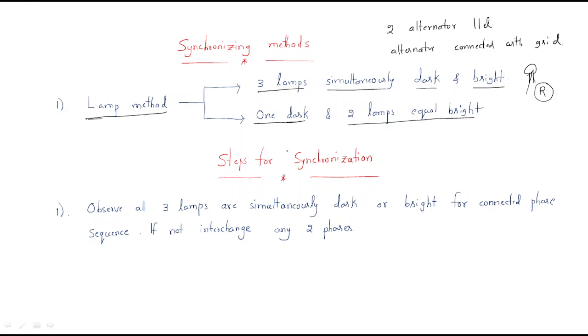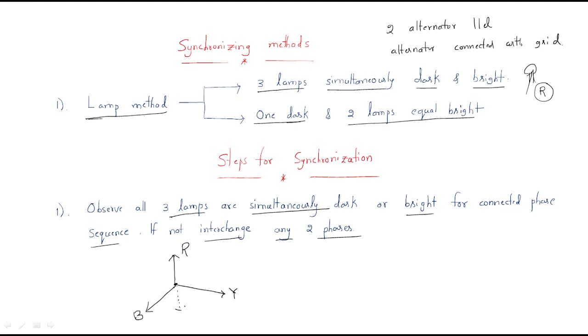The first step for synchronization: observe all three lamps are simultaneously dark or bright for connected phase sequence. If not, interchange any two phases. For example, we have R phase, Y phase, and B phase, and on the other side R dash, Y dash, and B dash paths.